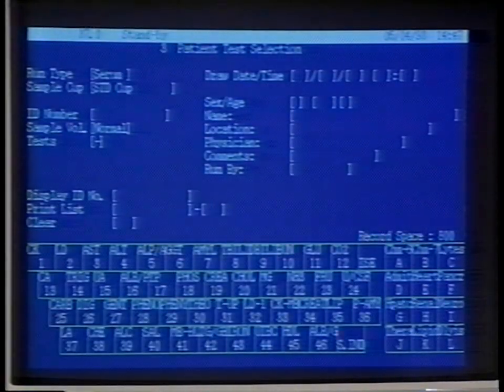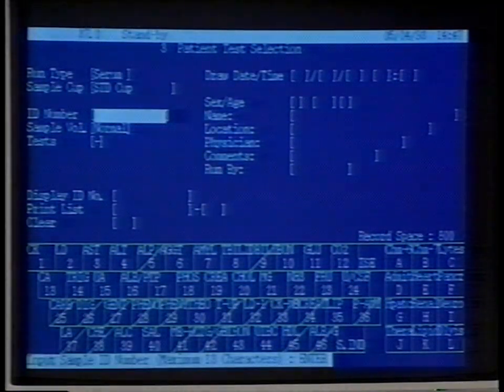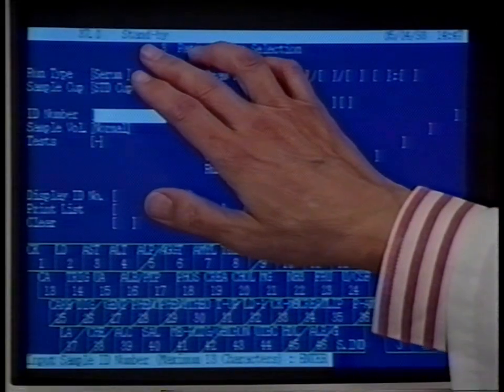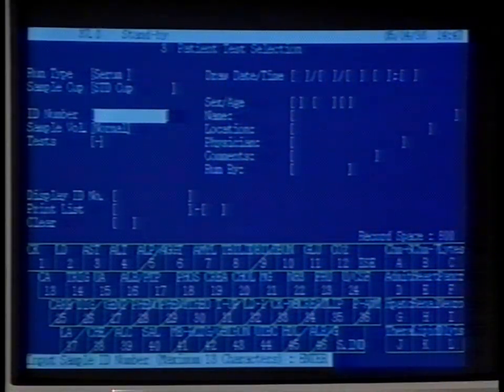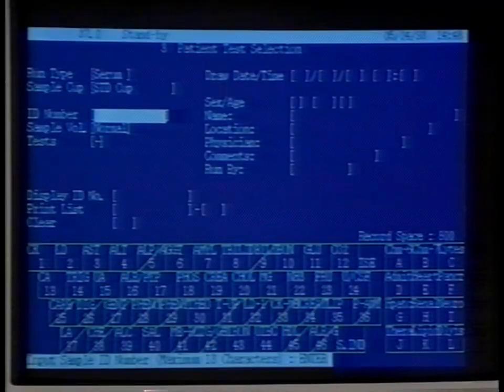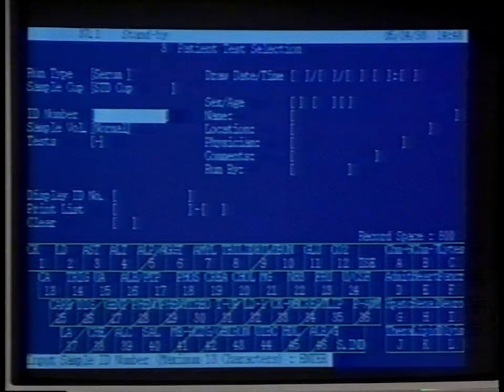There's a white status bar at the top of each screen which tells you what the analyzer is doing at all times. It displays such information as the incubation bath temperature, alarm status, operational status, the date and time. Here's an entry field highlighted with the cursor. These entry fields permit you to input information, and you can use them to specify certain control unit functions. Each entry field has help prompts, which appear at the bottom of the screen when the entry field is highlighted.